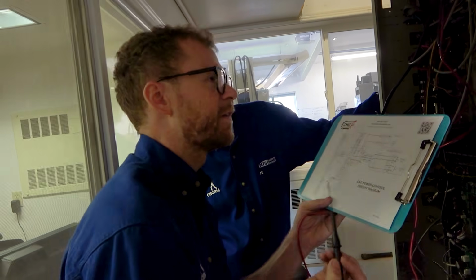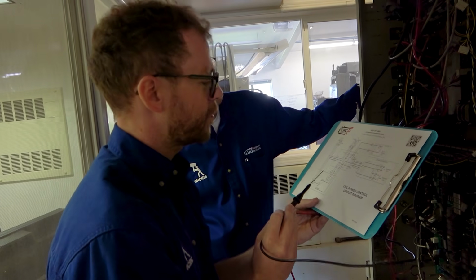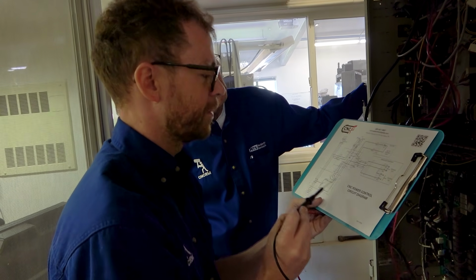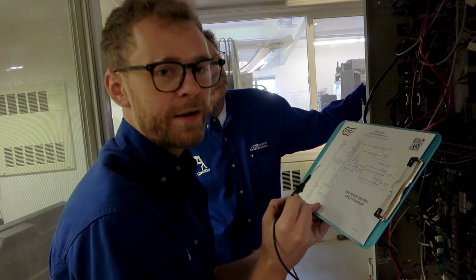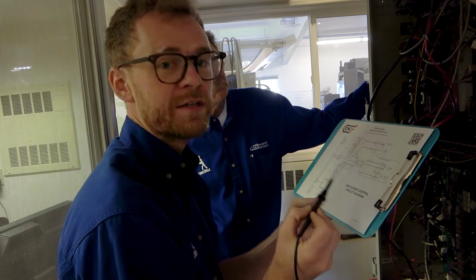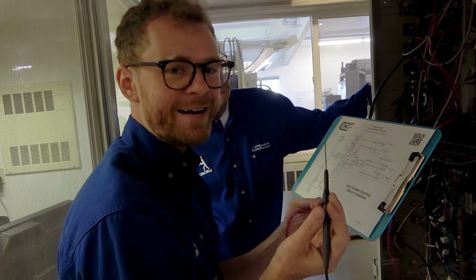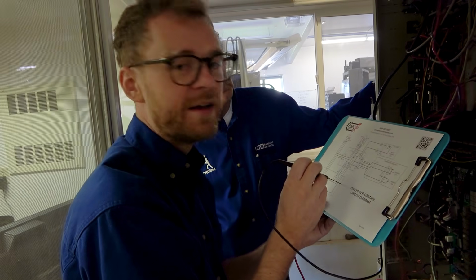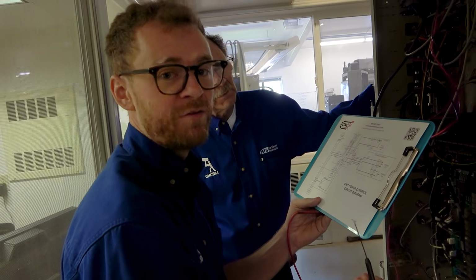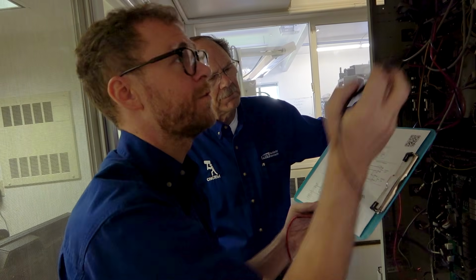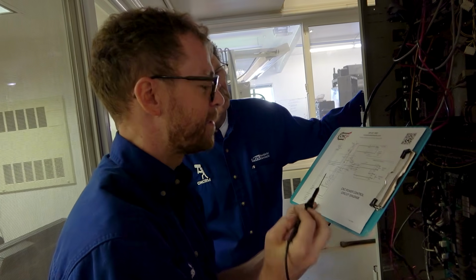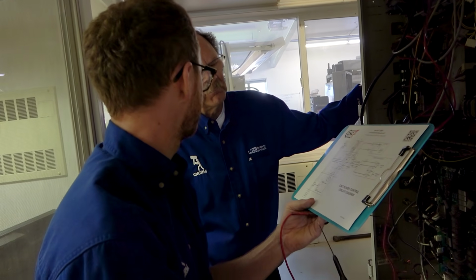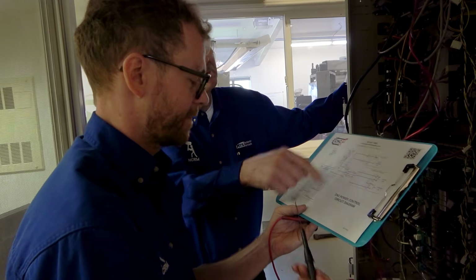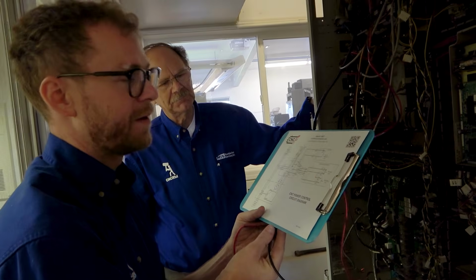So in troubleshooting this, we've got a difficult task of chasing the voltage. Somewhere in this circuit, we're losing voltage and something's not working right. But you've got to know where to put your voltmeter lead, where to measure the right voltage. Because if I just put it to ground or if I measure the incoming power, I'm not going to be measuring the right circuit. Well, we know this isn't pulled in physically. We know it's not pulled in.